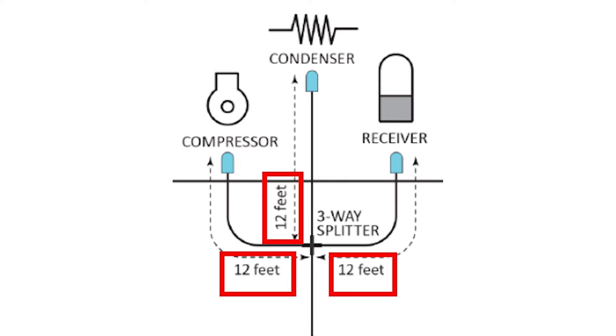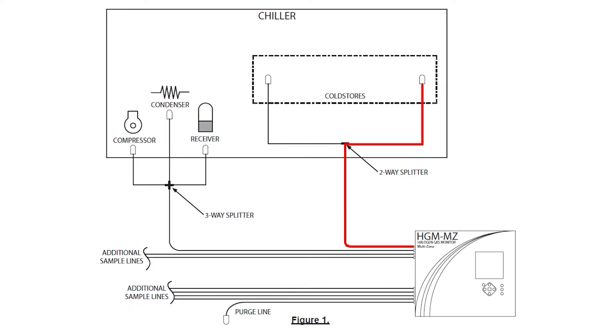All legs of a split must be the same length to ensure an equal sample draw from each of the separate locations. The total distance for a line utilizing a splitter should equal the total length from the monitor to the splitter, plus the length of any one leg of tubing after the splitter. Do not add up all of the leg lengths to calculate this distance.